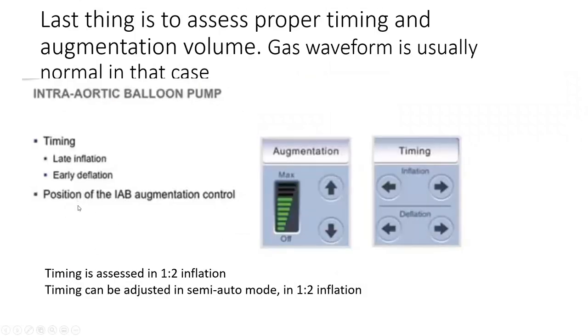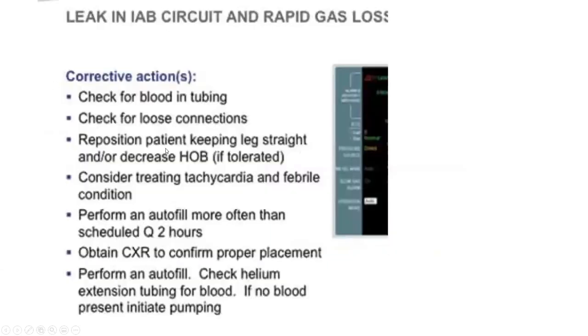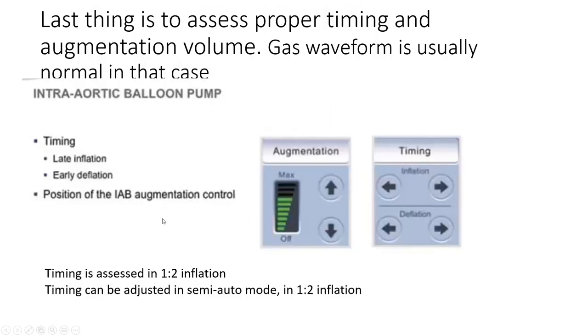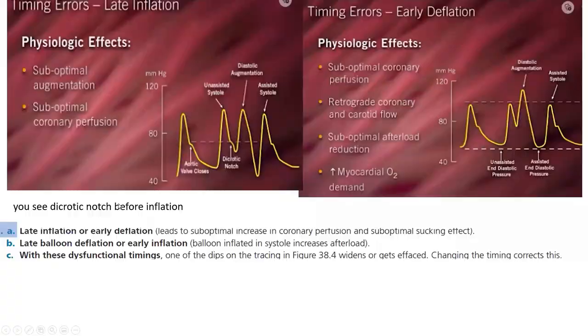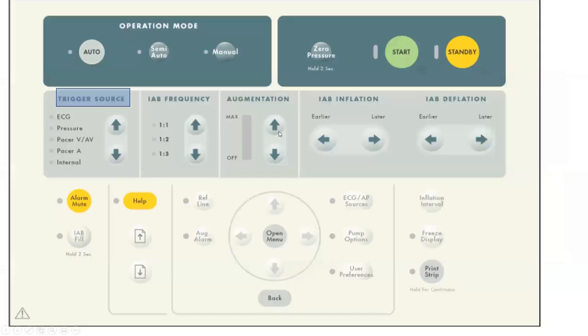So the last thing to check when you have poor augmentation, so I described most importantly the catheter issues, leak and kink. And I explained the patient factor. The third thing you check for is maybe poor timing issues, okay? Timing and poor augmentation. So there is a button here called augmentation. We always put it on maximum. If the patient needs balloon pump augmentation, this should be on maximum. Why give him less? You only reduce it if you're trying to wean it, and I'll explain that. So it should be on maximum.